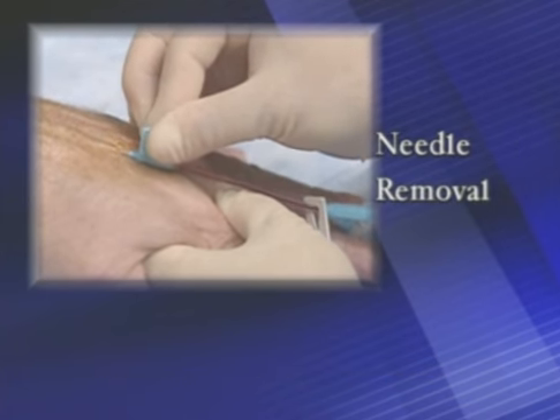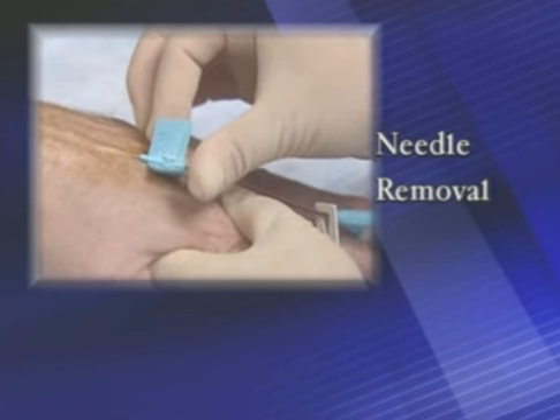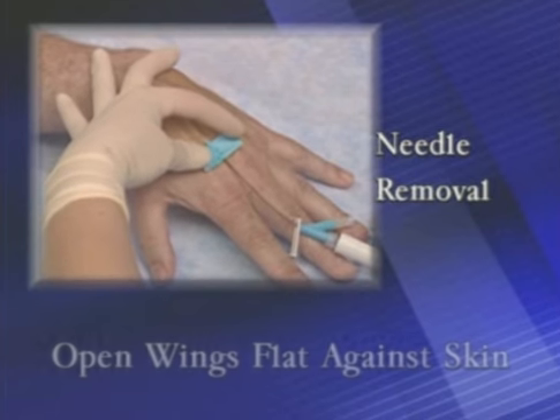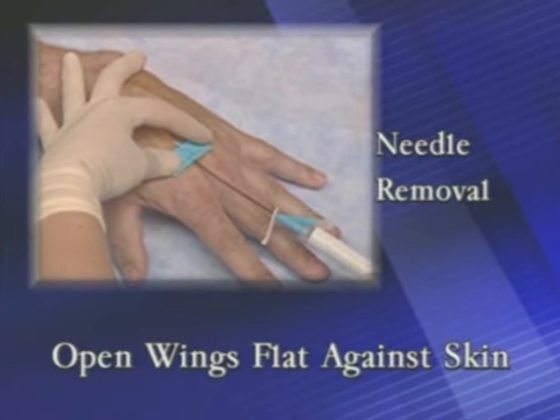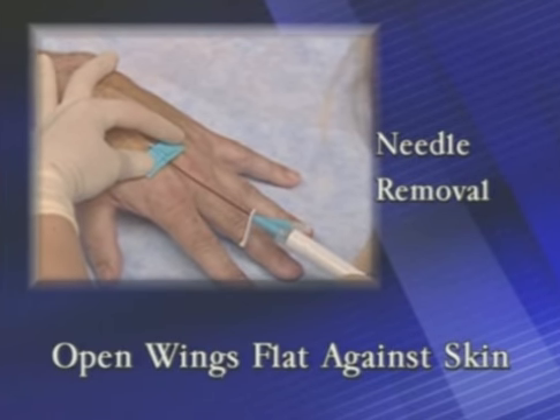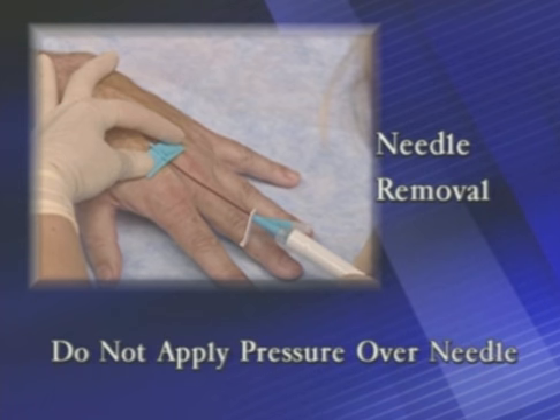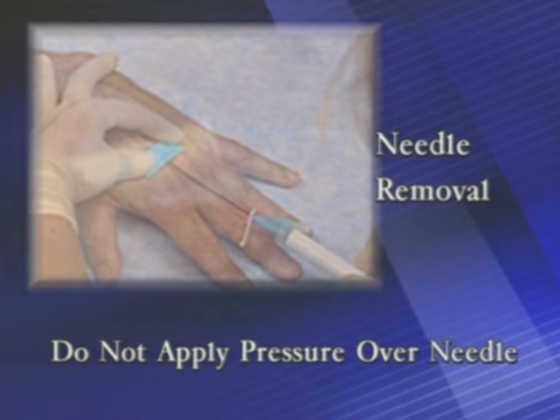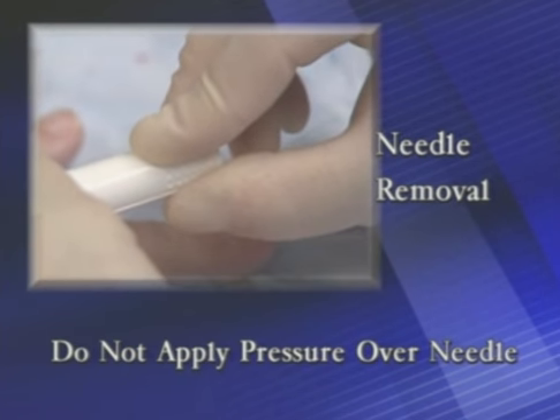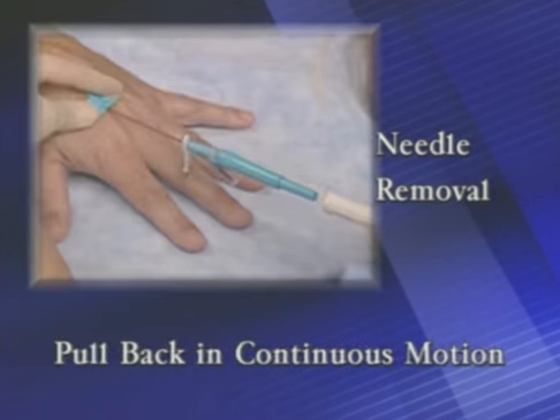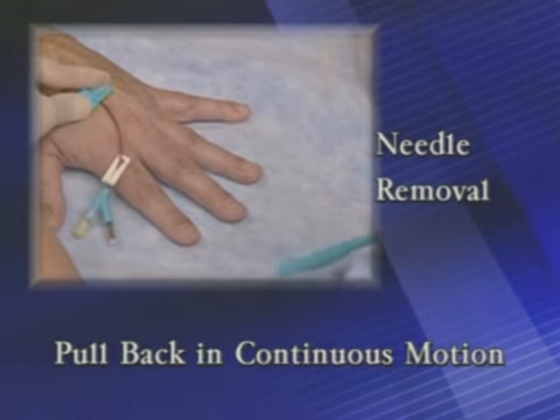To make removal of the needle as easy as possible, follow these simple steps. Open the wings flat against the skin and position your fingers on the center of each wing to secure the catheter. Don't apply pressure over the needle. Keeping the extension tubing straight, firmly grasp the pebbled area on the safety shield and pull back in one continuous motion until the shield pops off.